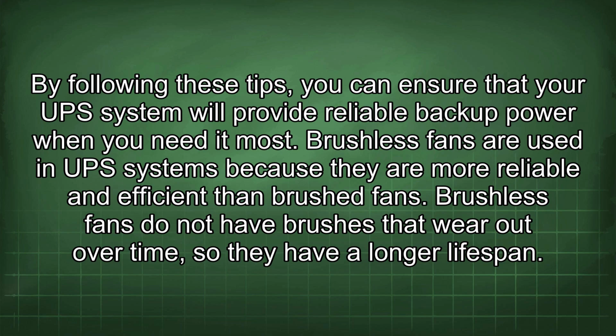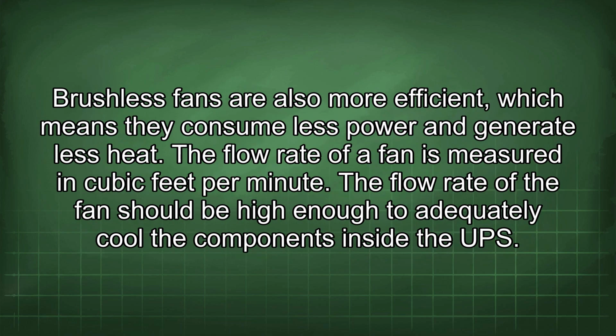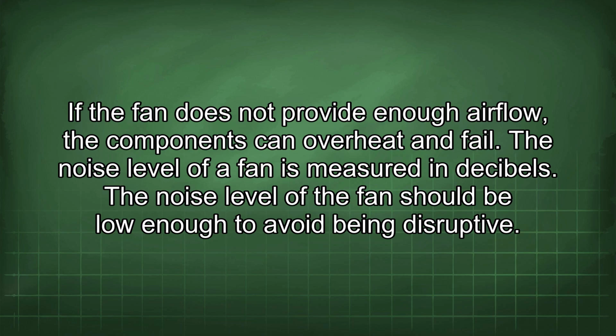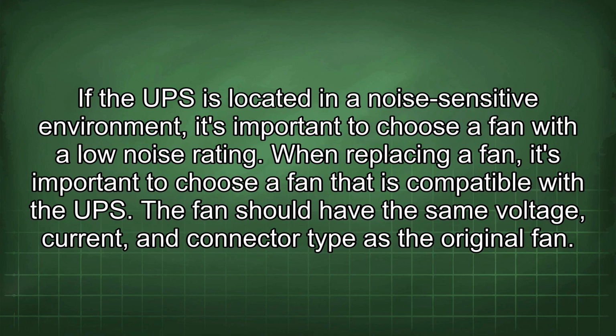Brushless fans are used in UPS systems because they are more reliable and efficient than brushed fans. Brushless fans do not have brushes that wear out over time, so they have a longer lifespan. Brushless fans are also more efficient, which means they consume less power and generate less heat. The flow rate of a fan is measured in cubic feet per minute. The flow rate of the fan should be high enough to adequately cool the components inside the UPS. If the fan does not provide enough airflow, the components can overheat and fail. The noise level of a fan is measured in decibels. The noise level of the fan should be low enough to avoid being disruptive. If the UPS is located in a noise-sensitive environment, it's important to choose a fan with a low noise rating.